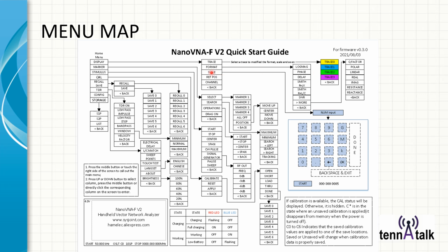So you can set the scale, the right-hand scale, and that's 0 to 1 in proportion to its default. So if you had a 1 to 10 SWR scale, and you change this scale number to 0.5, then it'll go from 1 to 5, which is 0.5 of 10, half of 10. So that's how that works. Channel will select whether you're talking S1P or S2P, and that's very important when you're doing log mag type through measurements.